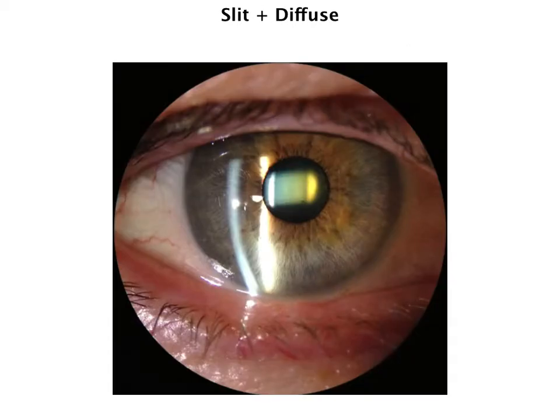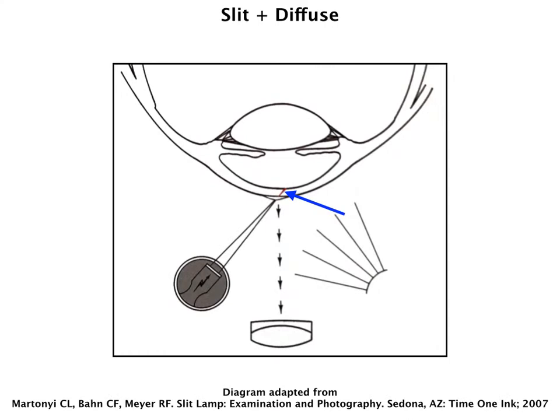If we look at the same photograph but now add just a little bit of diffuse light, we see that it kind of improves the overall quality — not just of the background, but also of the specific pathology that we're looking at, which in this case is the vacuoles. You can either put the diffuse light on the opposite side of the slit beam, or you could put it on the same side. One of the benefits of having it on the opposite side is it gives a little bit more even illumination.